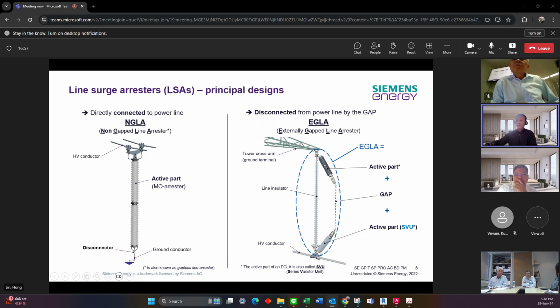In such a case, both SVUs, or the one SVU, will have a residual voltage, and this residual voltage can limit the voltage drop from this point to the other point, and this will limit the lightning overvoltage to a very low level. For example, it will be roughly 50% or 60% lower than the basic insulation level of the insulator. So with such measures, you will never have flashover on this insulator again.